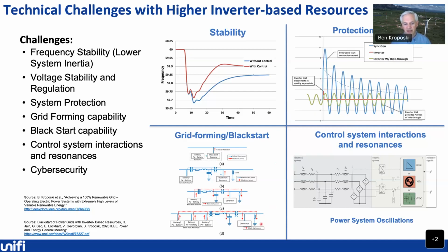Grid forming and black start is going to be increasingly important, just making sure that we have inverter-based resources that are capable of restarting the system from a blackout condition and providing system restoration, and are integrated with whatever type of system restoration processes we have for the grid. And there's a lot of specific details on what you need to take into account when you're looking at having your inverter-based resources provide that capability.